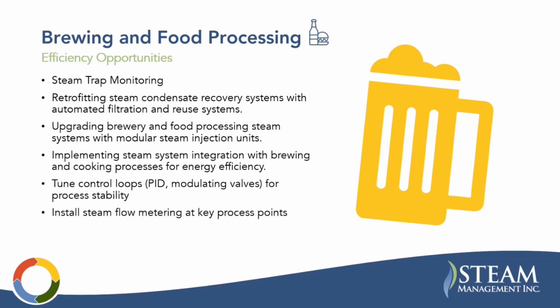Efficiency opportunities here: many of the common opportunities apply, but more specifically, steam trap monitoring makes sense in these facilities. Retrofitting steam condensate recovery systems with automated filtration and reuse systems. Upgrading brewery and food processing steam systems with modular steam injection units. Implementing steam system integration with brewing and cooking processes for energy efficiency. Tuning control loops to more properly control steam use, and metering and monitoring at key process points.